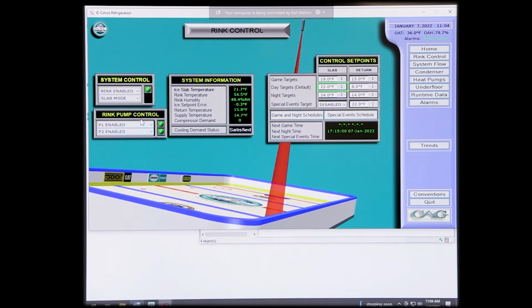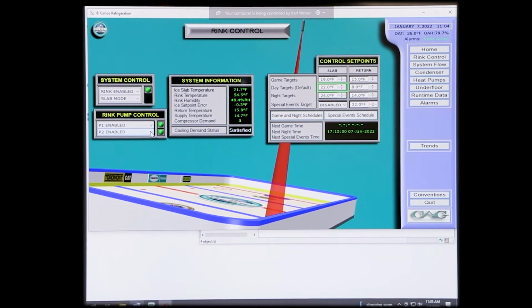In this particular screen, we have rink pump control, P1 and P2. These are your two cold floor pumps. Now, within the other screens, we also have control over these pumps. God forbid we've lost a shaft seal or we have a problem with a VFD drive. We need to be able to tell the computer that we do not want to run that pump, use the other one. So we would go in here and disable that pump. I'll do an example here. I'll disable P2. Now, if I was in the operator screen, it wouldn't allow it.